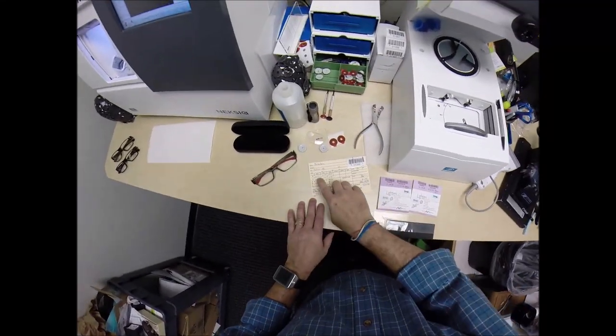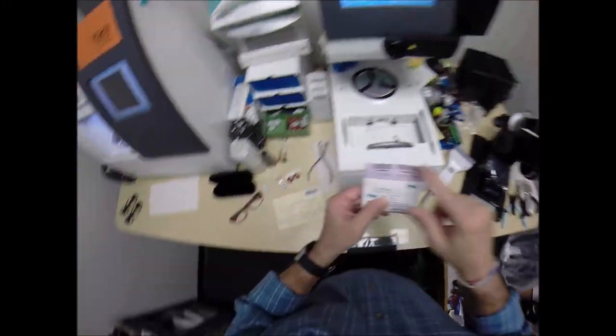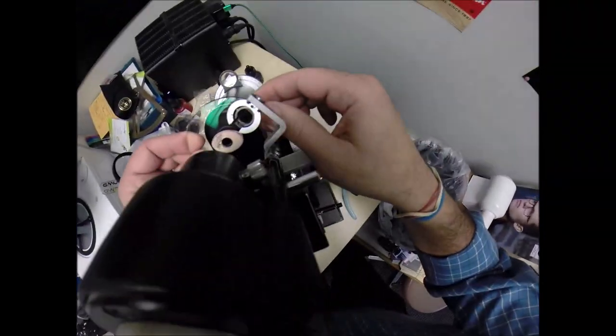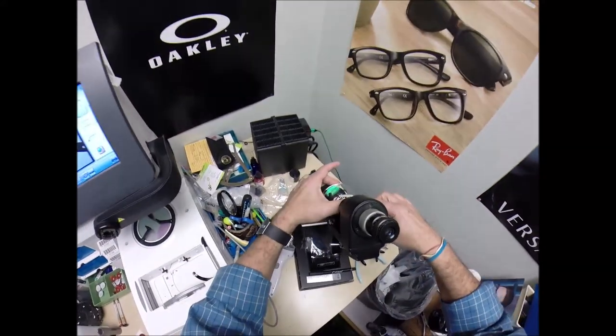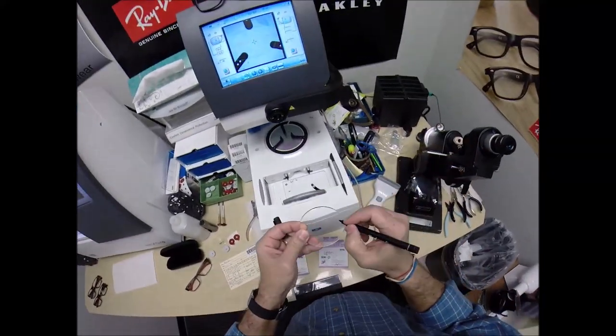Your right eye reads -1.25, -0.75 at 85. Put the axis wheel on 85, the power drum on -1.25. Take the lens out of the protective sleeve. Rotate the lens until the spherical component comes into view first. Check your astigmatism correction. That looks good. Put 3 dots on your lenses. The ink has not dried off yet. This is the right lens.